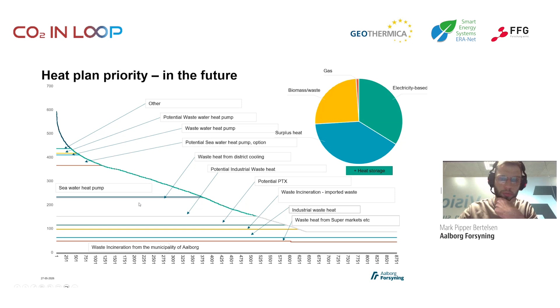To talk a little about the district cooling systems we have right now: we have one supplying cooling to the large super hospital, which is almost done being built. I think they're moving in this month and trying the full scale test as well. We have a contract to deliver 7.3 megawatts of cooling from a limestone lake, through a heat exchanger, into a cooling central where we have both chillers and heat pumps. If the lake is cold enough to supply the hospital with cooling, we just bypass this cooling central.